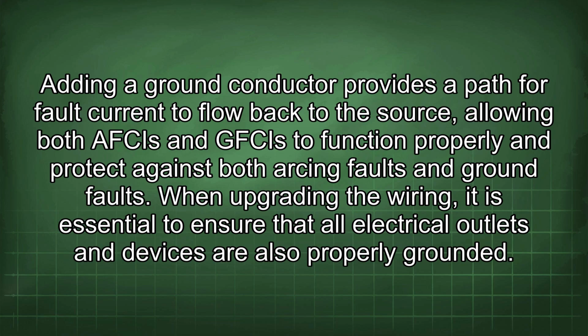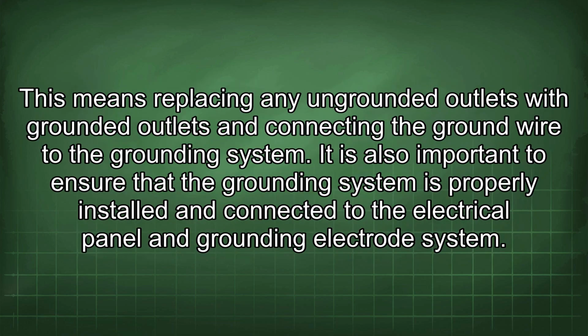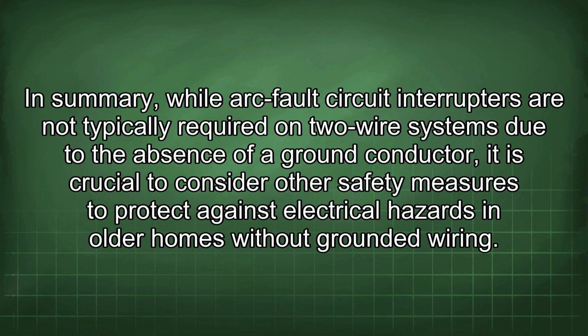When upgrading the wiring, it is essential to ensure that all electrical outlets and devices are also properly grounded. This means replacing any ungrounded outlets with grounded outlets and connecting the ground wire to the grounding system. It is also important to ensure that the grounding system is properly installed and connected to the electrical panel and grounding electrode system.